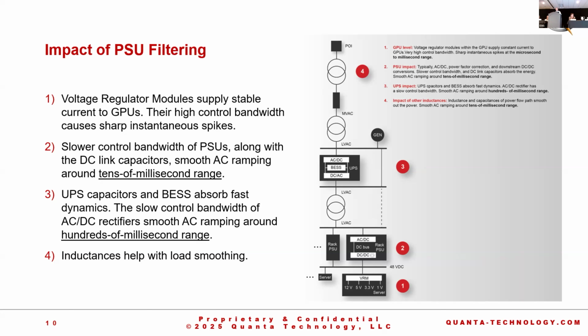Following that, you have a DC link, which I haven't shown here, unfortunately. We call it the DC link capacitor, 430 volt, and then you have DC to DC choppers that bring the voltage to 48 to 50 volts, depending again on the mode. That cap bank also helps with smoothing some of the loads. In general, the PSU will smooth out the load over tens of milliseconds, roughly 50 to 70 milliseconds, based on some of the tests we have done.